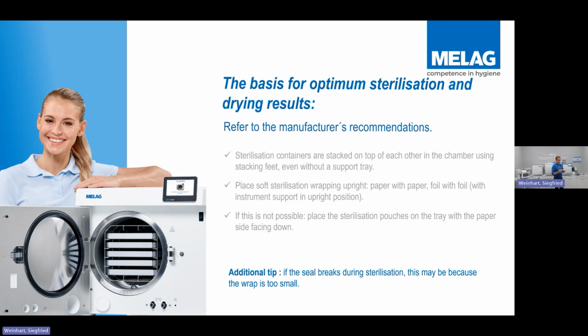It is really important when we put our pouches in that we don't overload the pouches. So if we're using self-seal pouches, which a lot of the UK are, then self-seal pouches tend to be available in a variety of different ranges. What you'll tend to find is you'll never find a pouch that will exactly fit what you want it to fit, certainly if it comes down to using clip trays, for example. What tends to happen is you'll buy a pouch that's too big and then you fold it over.